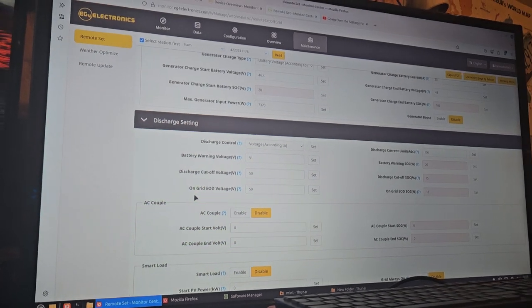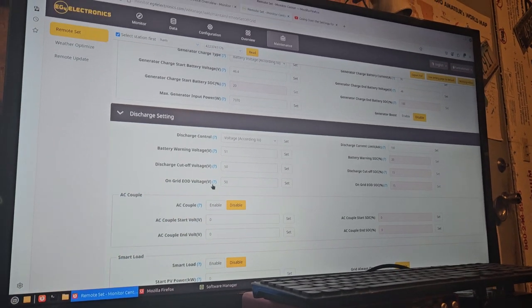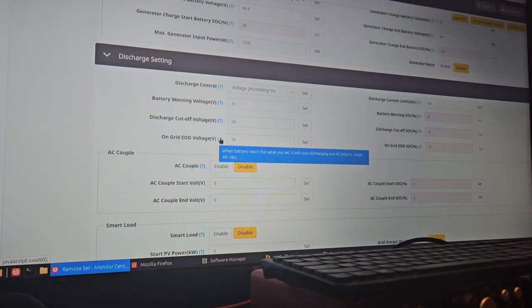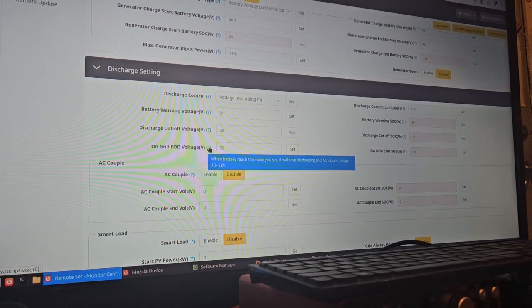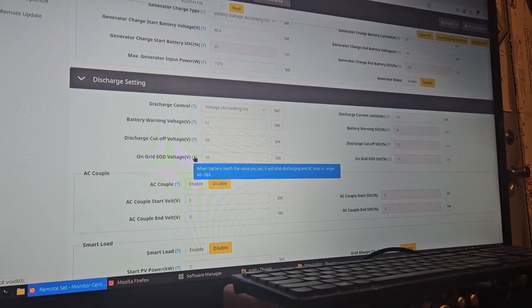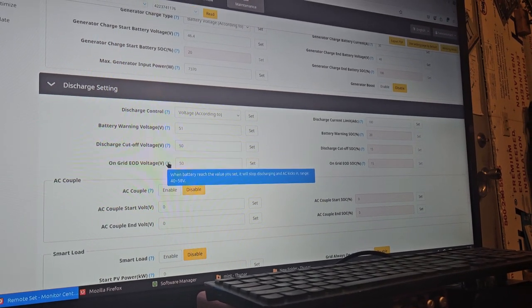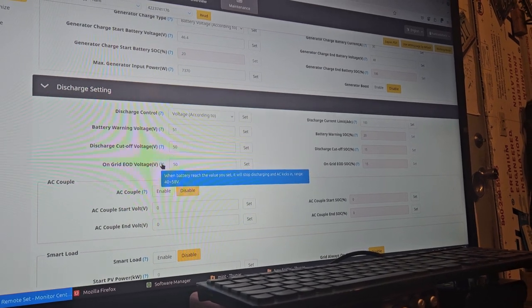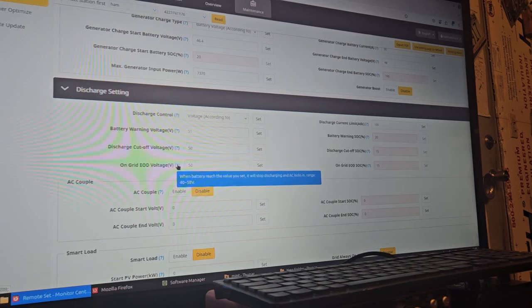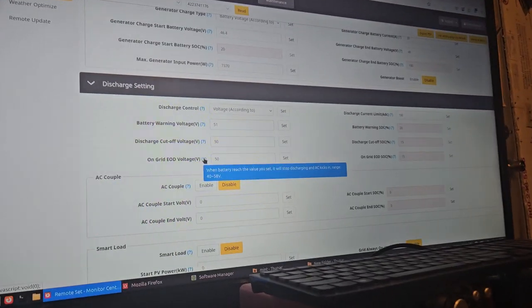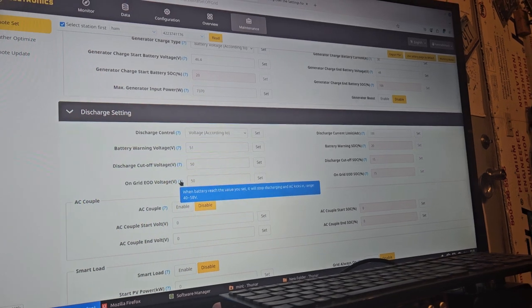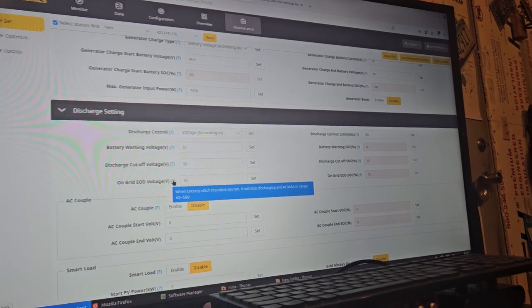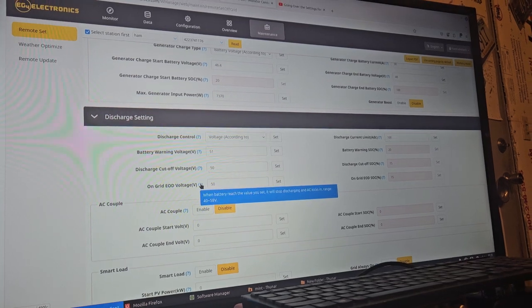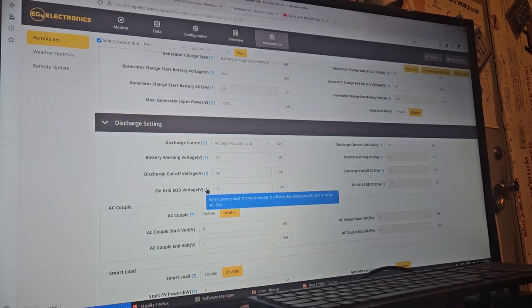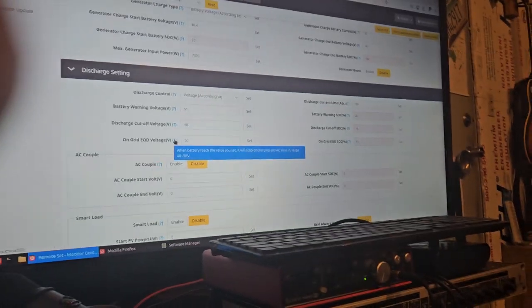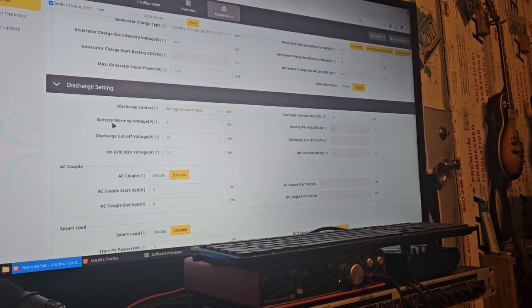You can hover over the question marks on any of these settings. It says, in Chinglish, 'when battery reach the value you set, it will stop discharging and AC kicks in,' ranging between 40 and 58 volts. So when the battery reaches the value you set, it stops discharging and the AC kicks in — the battery stops discharging at 50 volts, the AC kicks in, takes over the load, and charges the battery at the same time.